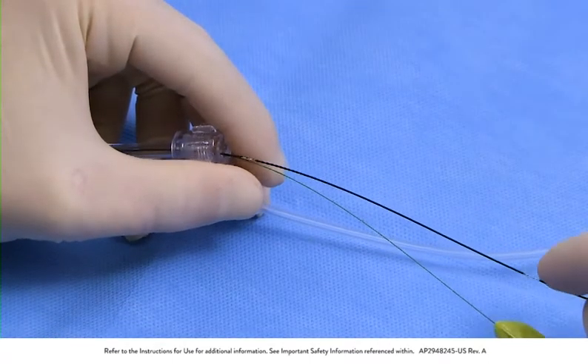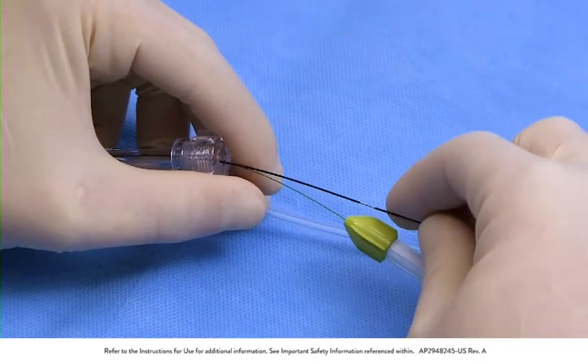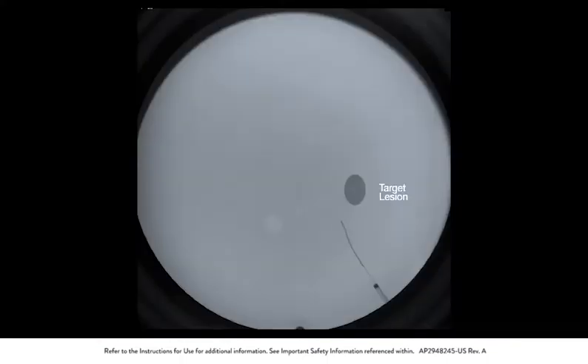Advance the delivery catheter through the guide catheter or introducer sheath to a location proximal to the lesion. Advance the bare wire across the lesion.